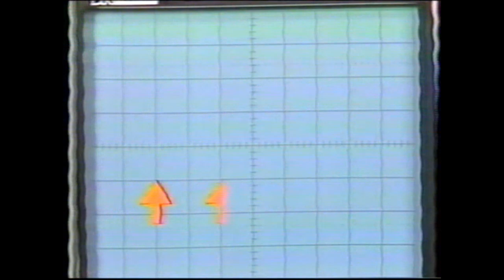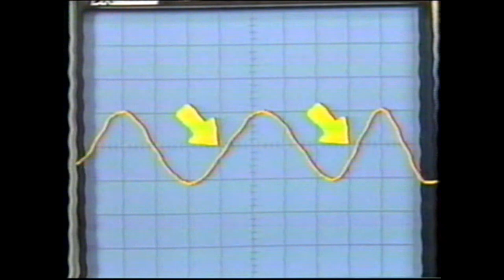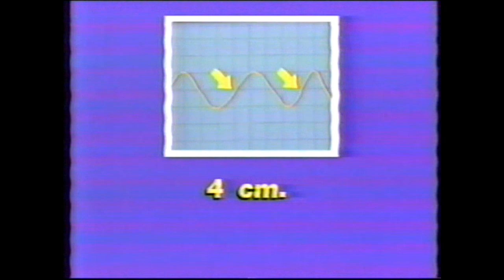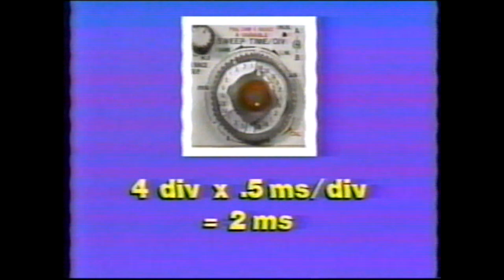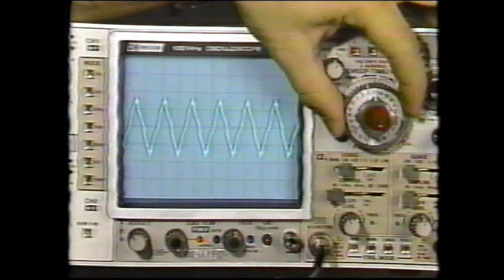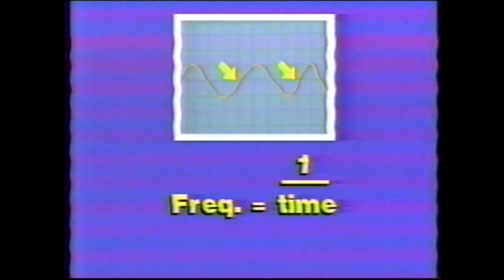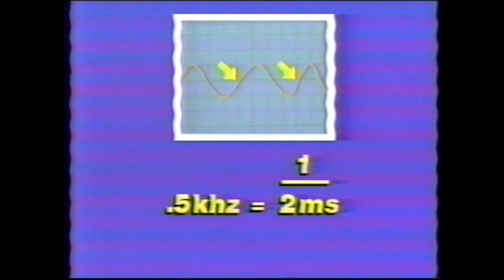The time base control pertains to the time value of each graticule division horizontally. A specific time period can be measured by counting the number of centimeters on the x-axis that the time period covers. Then multiply that by the time base setting. Changing the time base setting changes the number of cycles shown on the CRT. To determine frequency, calculate the period of time it takes to complete one entire cycle and divide the result into 1.